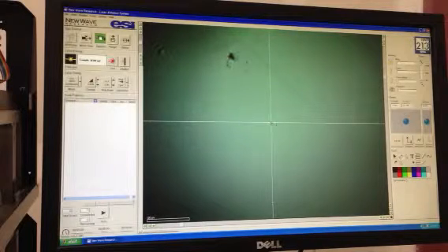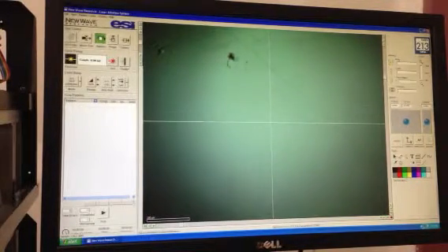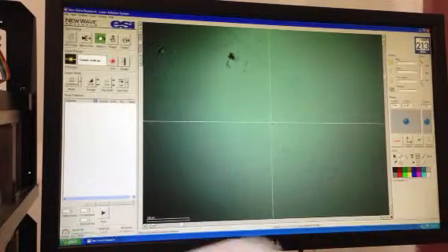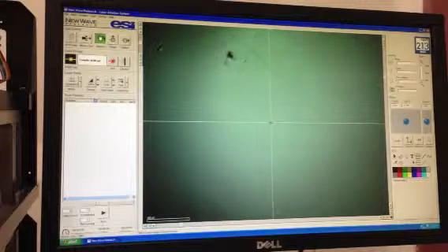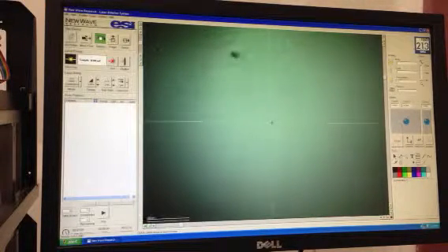So from the crosshairs to the center of our target spot, I'm measuring the distance. And this distance, you may not be able to see it, but X equals 3, Y equals 3.5. So we'll record this in the table under from -X -Y. Then after this, the next step is to find the center position, go to that center position again, basically correct it, just so we're starting with everything basically perfect.